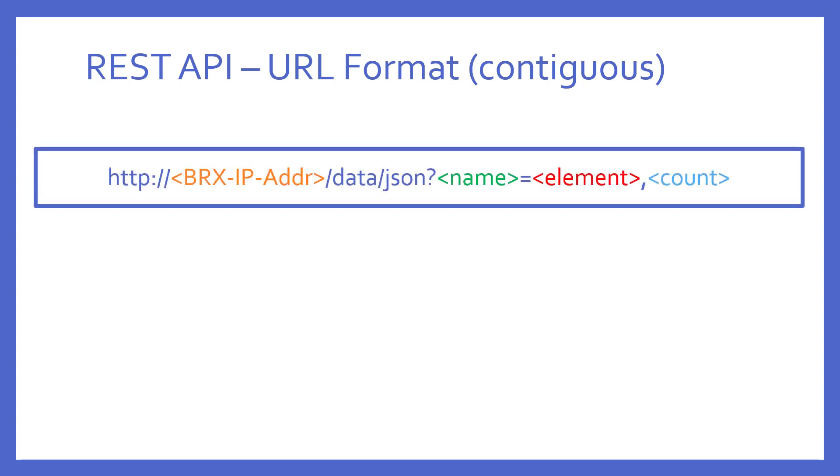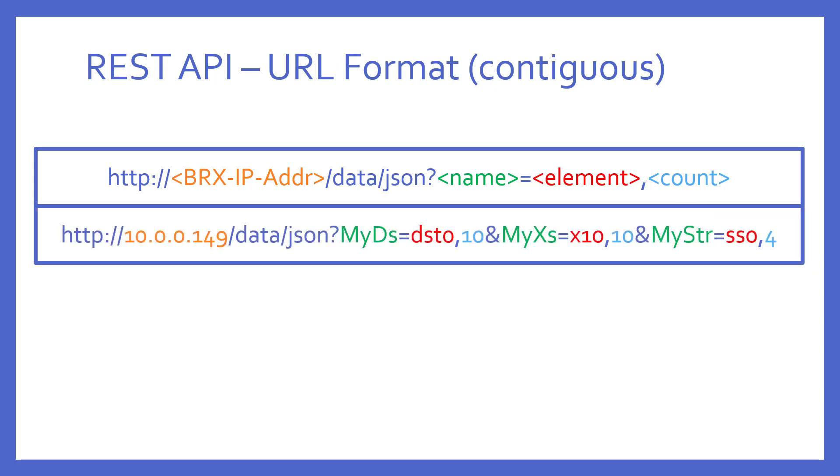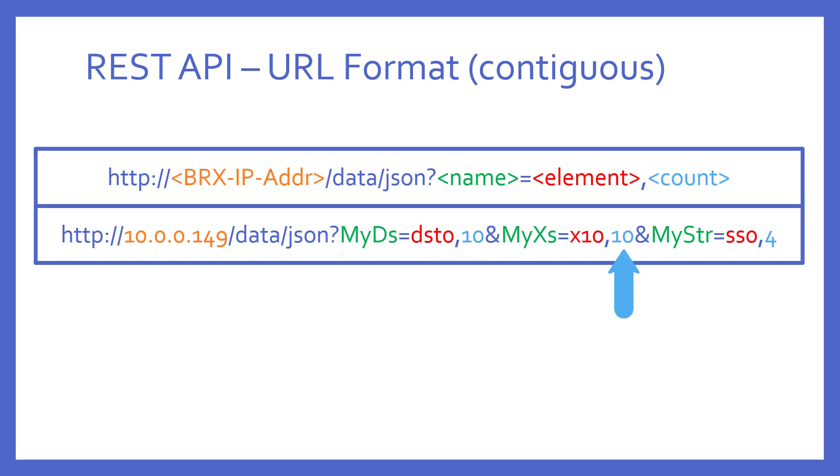What if I wanted several contiguous elements? To get contiguous elements, I merely have to follow the name equals part with a comma and a count. This count can be up to 128. So, in this example, notice I am getting 10 DST starting with DST0. And then I am using an ampersand to get another group of 10, X's this time, starting with X10. And then four strings starting with SS0.